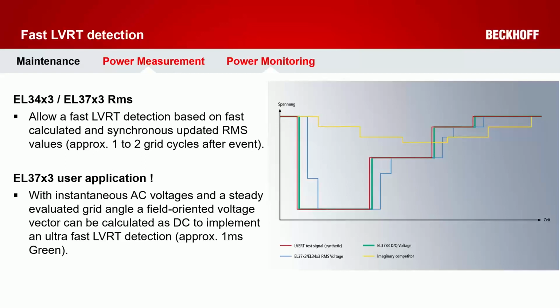In existing and old applications, we find a lot of monitoring units using extra fieldbuses, and maybe with not optimized RMS calculation. So now I will introduce you to our terminals. For this, I have added a reference generator which allows a voltage dip as a reference with a defined envelope. And here you see the result. So our standard terminal is the EL34, but also the EL37, with their integrated and external calculated RMS values, are able to follow the reference as fast as possible based on the RMS values, which are updated synchronously at each zero cross of a grid period.